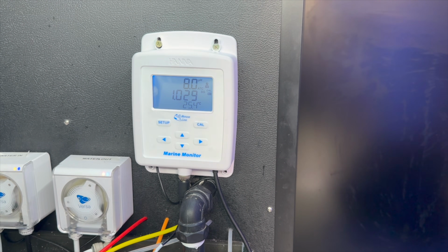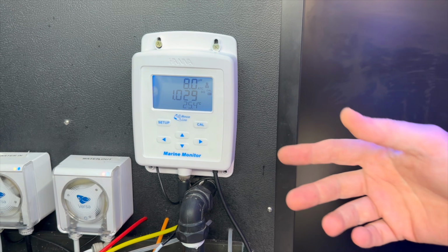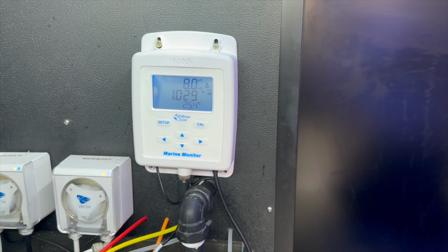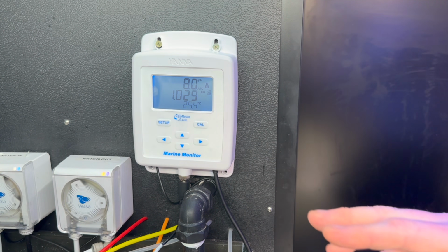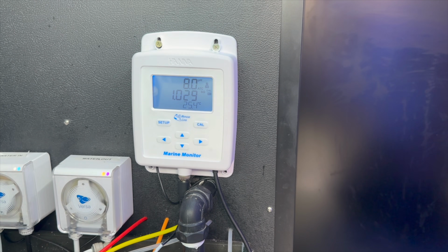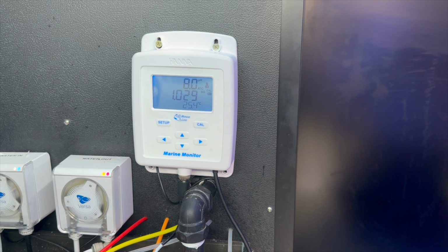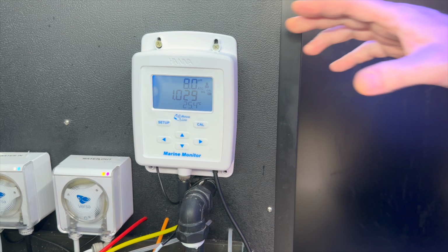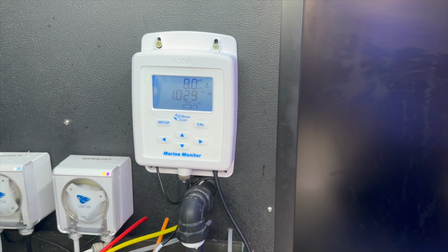So two things: the included pH probe that I got with my unit seems to be defective and throwing some sort of bizarre signal, which was affecting the specific gravity probe. And secondly, I did find the factory power supply that came with the Australian delivered units anyway to be of poor quality. When I switched over to a higher quality power supply, the device now works as expected.